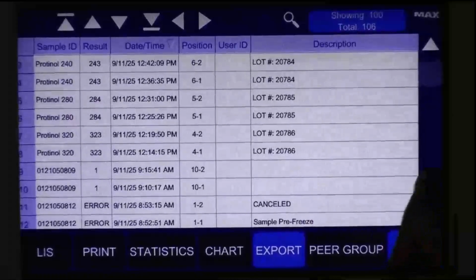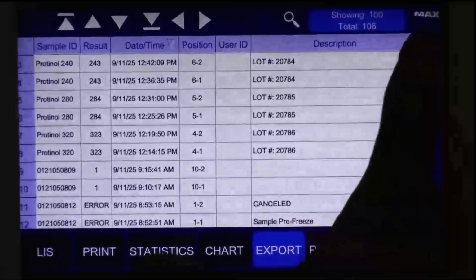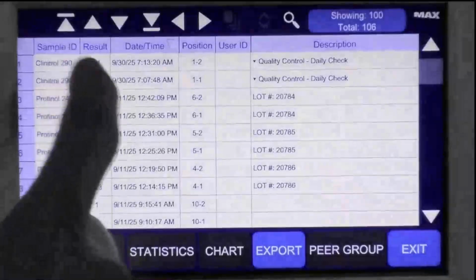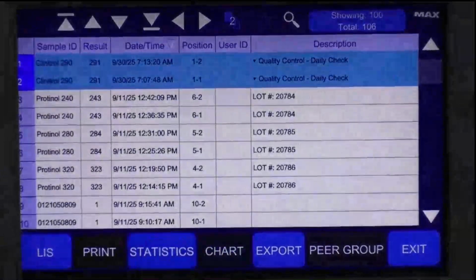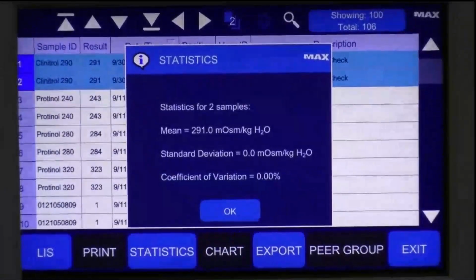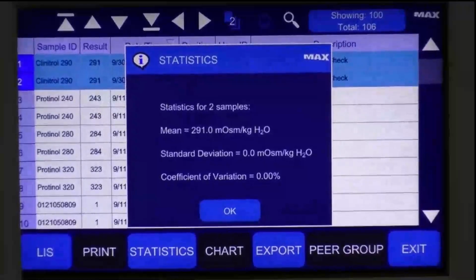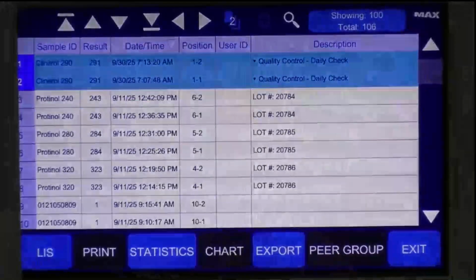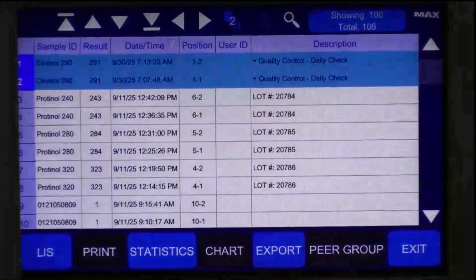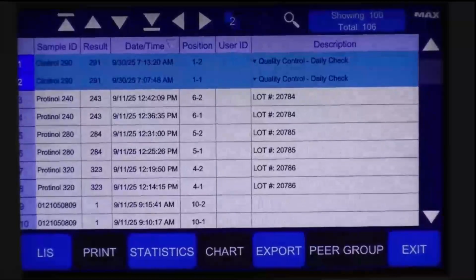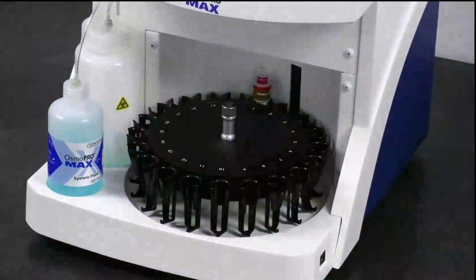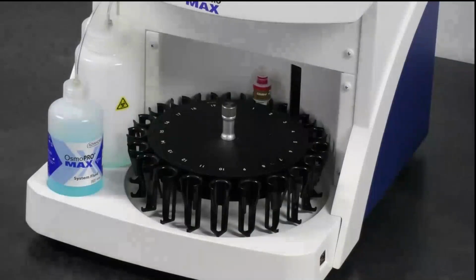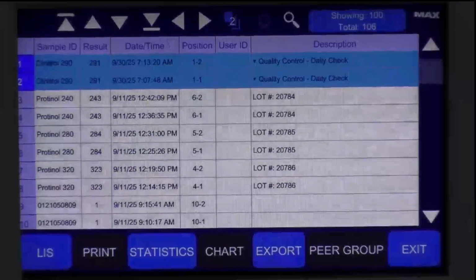Let's say we want to run statistics on these 2 clinitrols. Then we can hit that. And that's actually going to give me the mean, the standard deviation, and the coefficient of variation. Obviously, those results came in exactly the same. So that looks really, really good for us. If I wanted to export to our USB port, which is over here on the right side of the instrument, it would export any selected results in a CSV format, so Excel compatible.